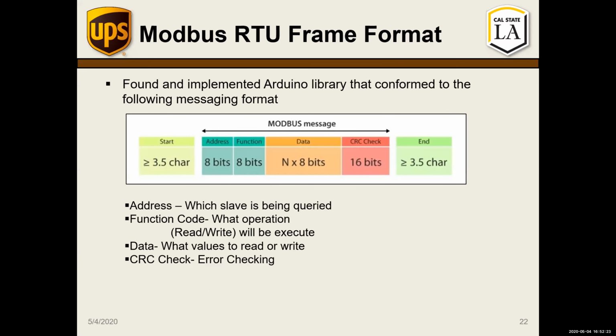This image shows what we were trying to implement, called a frame format for a message. What's cool about the Modbus structure is that it has a component called a function code, which essentially says, this is the operation I'd like to run—whether a read or write, and whether we're writing to individual bits (bit-specific addressing) or to an entire register. Then we have our data, and then a CRC check, which is essentially an error check, at the end.